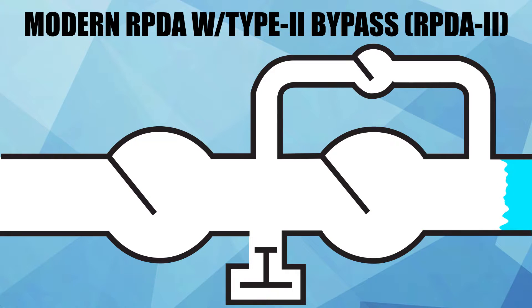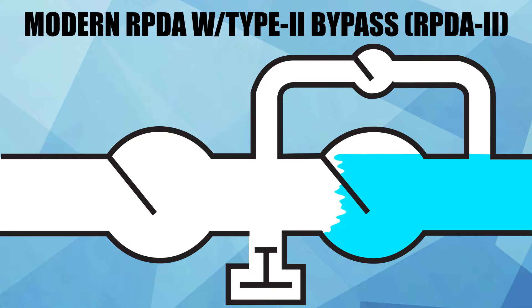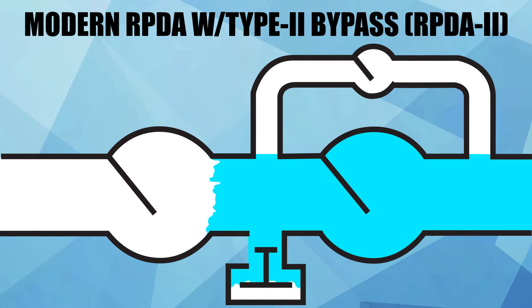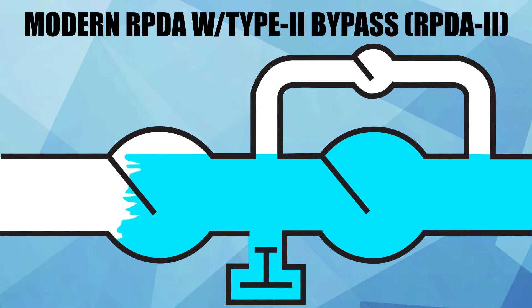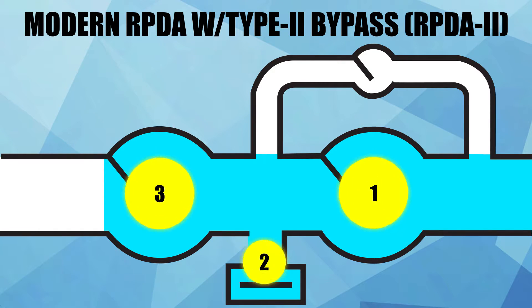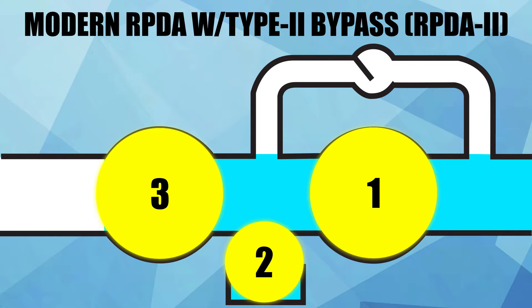During a backflow condition on a modern RPDA with a Type 2 bypass, the water first encounters the main valve second check. Next, the water encounters the main valve relief valve. And then the water encounters the main valve first check. This also provides three mechanisms of backflow protection.